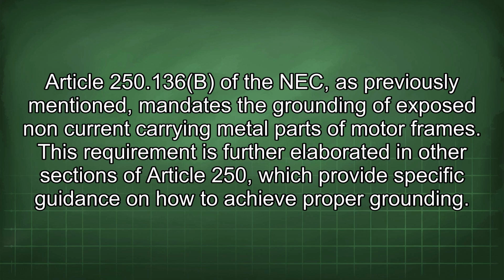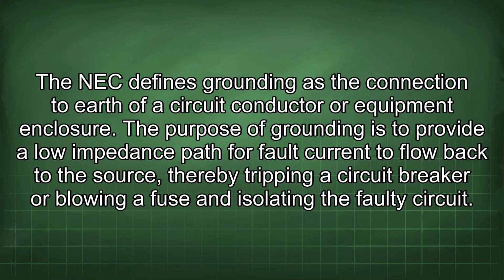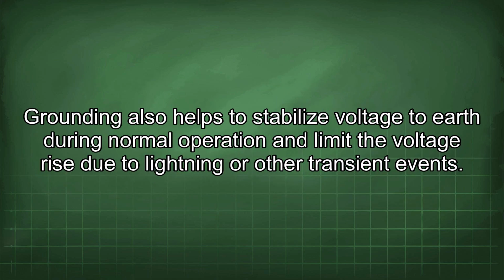This requirement is further elaborated in other sections of Article 250, which provides specific guidance on how to achieve proper grounding. The NEC defines grounding as the connection to earth of a circuit conductor or equipment enclosure. The purpose of grounding is to provide a low impedance path for fault current to flow back to the source, thereby tripping a circuit breaker or blowing a fuse and isolating the faulty circuit.